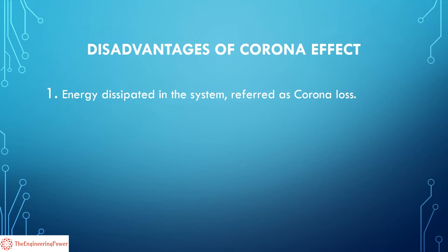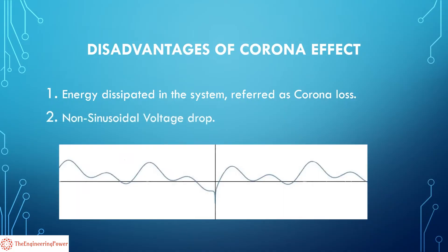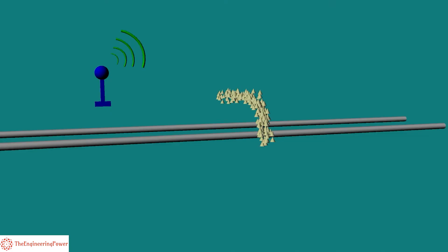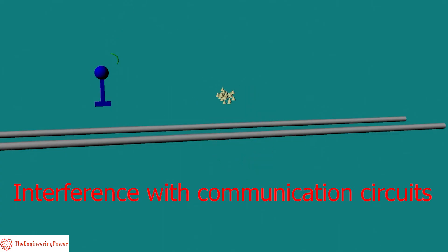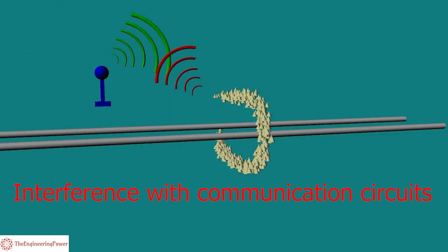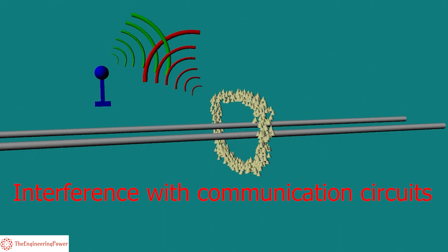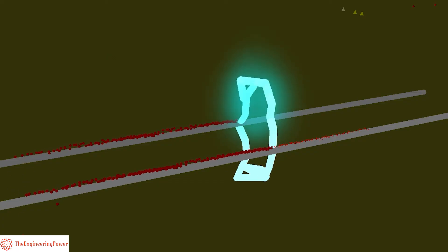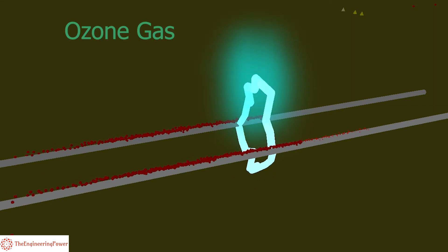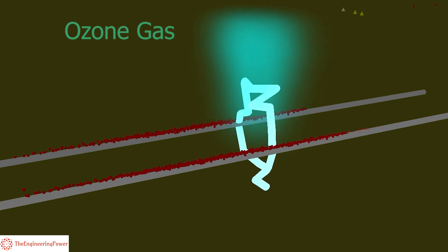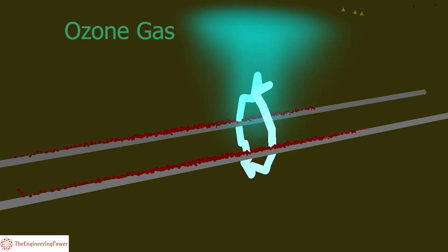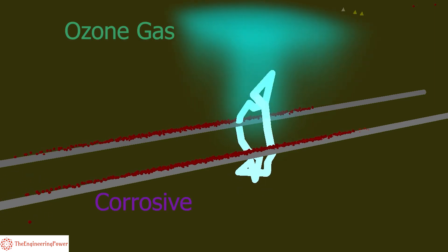A non-sinusoidal voltage drop occurs in the transmission line due to corona effect, which causes interference with neighboring communication circuits. Corona effect also results in the production of ozone gas, because of which the conductor becomes corrosive.